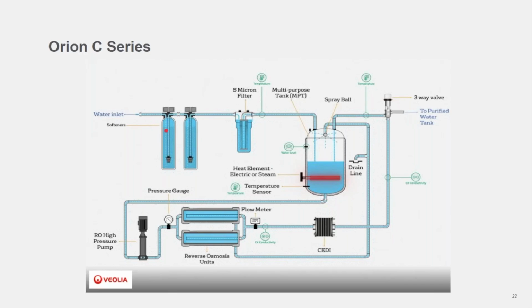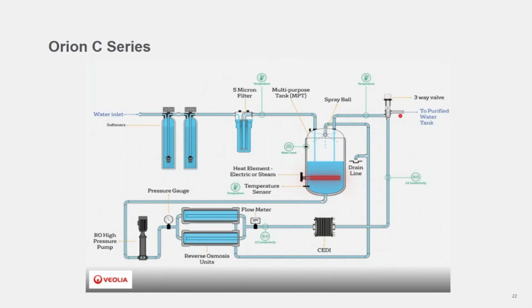So we go through a set of softeners in series, and from the softeners it goes through a 5 micron filter and then into what we call a multi-purpose tank, like a break tank. From the break tank, the water is repressurized through the RO units, and then the RO unit feeds the CEDI, which brings down the final conductivity less than 0.2. Then we go off to the three-way valve, which is positioned on top of the purified water tank, and then it either fills the tank. If the tank is full, it recycles back into the multi-purpose tank. As we say, it's a multi-purpose tank.